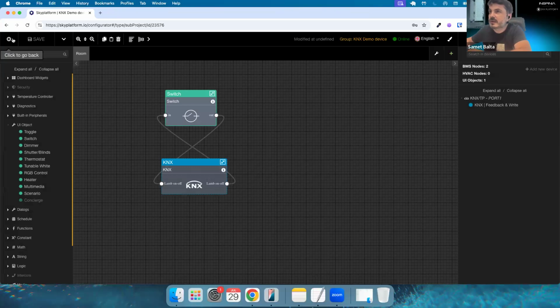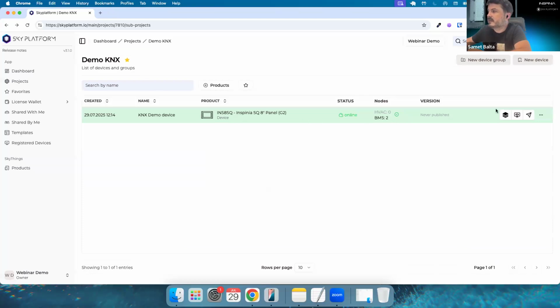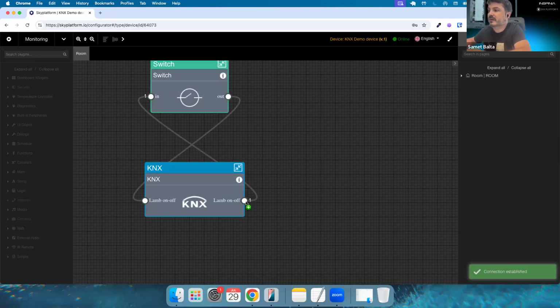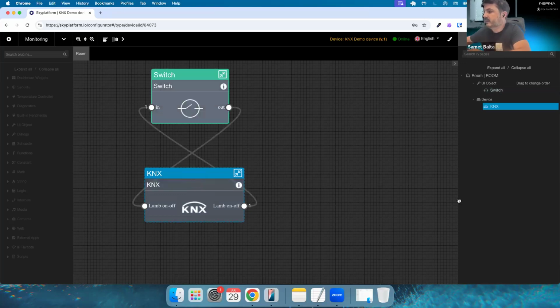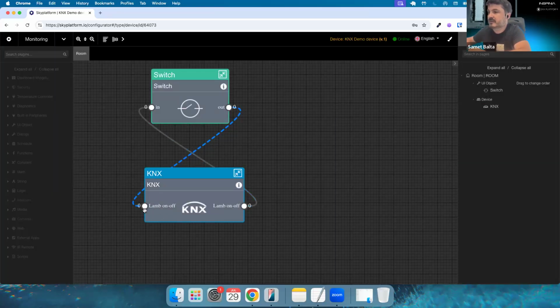Then I need to save this project, so the configuration is being sent. Then I need to go to the list section and find our device, and then publish it. In a quick moment, our touch panel will be updated. I can see the touch panel is updated, and I will show you the monitoring tool here. When you click the monitoring tool, you will see the latest status. As you can see, our KNX has one. I mean, our switch is open and is being sent to the switch, but I want to change it through the touch panel. Now I will click the touch panel. Yeah, I closed the switch and the lamp is closed. Then I can open it again. You can also send these values from here. I mean, I will set this input output 0. Then KNX status is being changed.